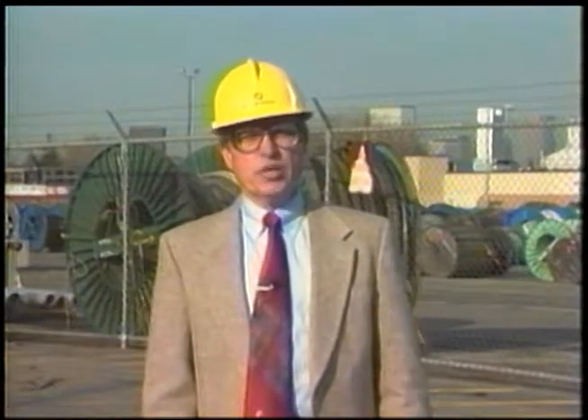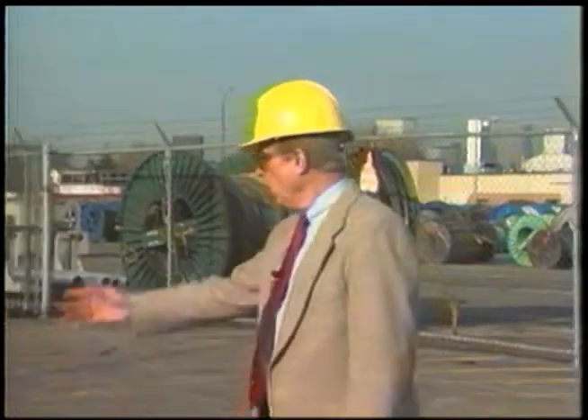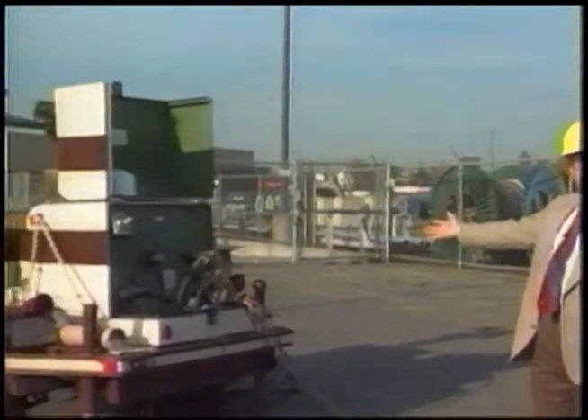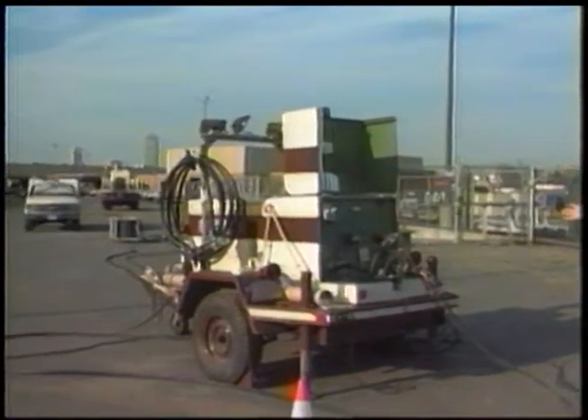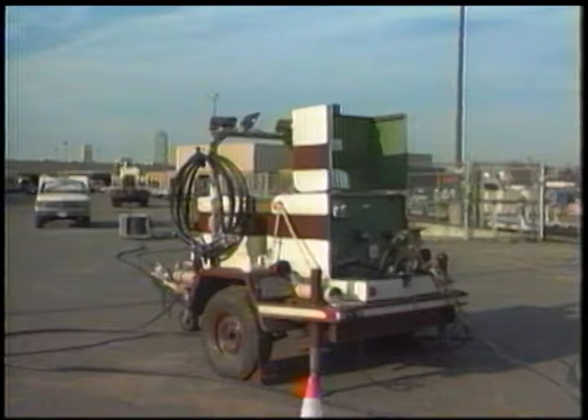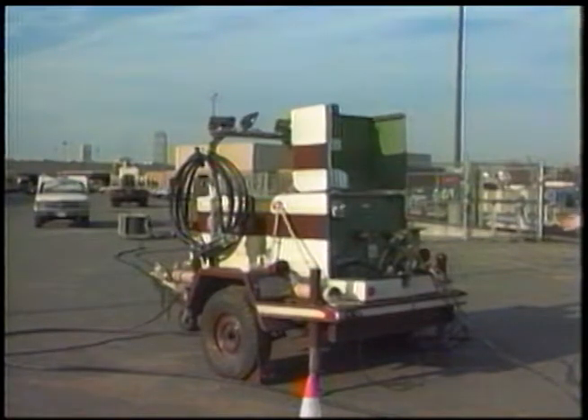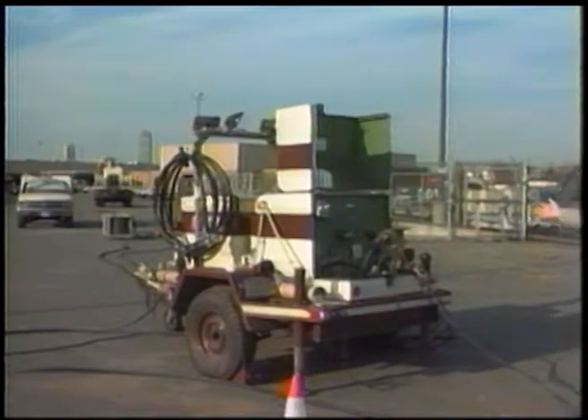This is the second demonstration. This is going to be a 15 kV fault. In order for us to do this demonstration, we're going to use this portable transformer, which will become energized by a generator. The transformer is going to take 120 volts and boost it up to 8,000 volts.